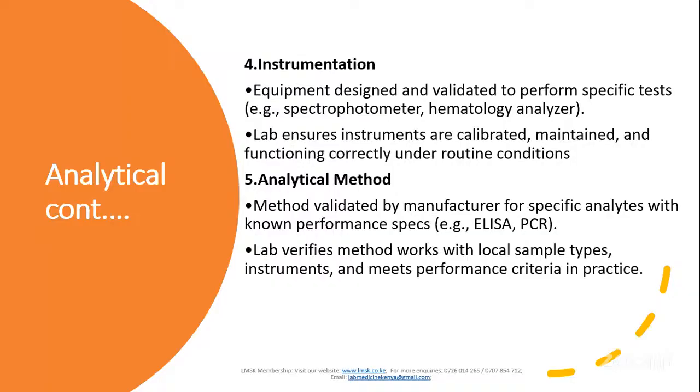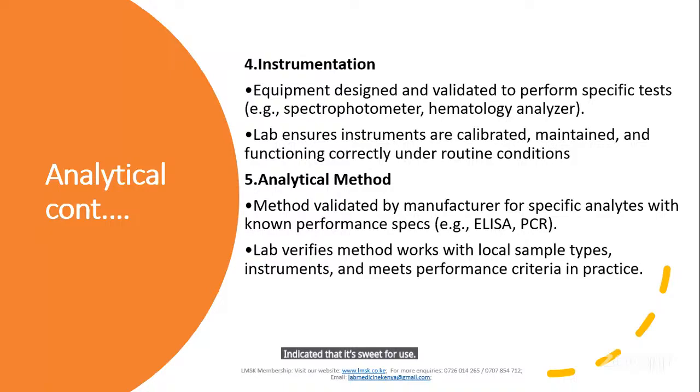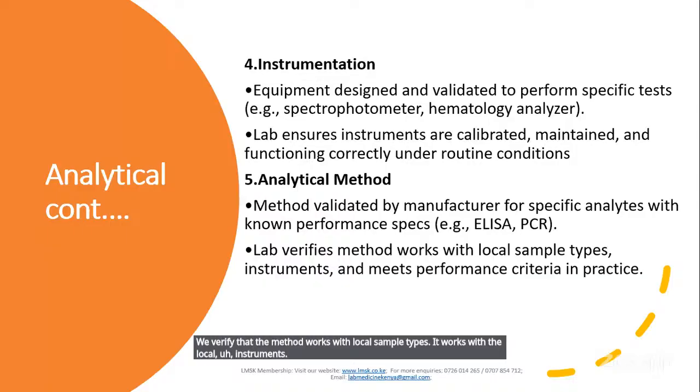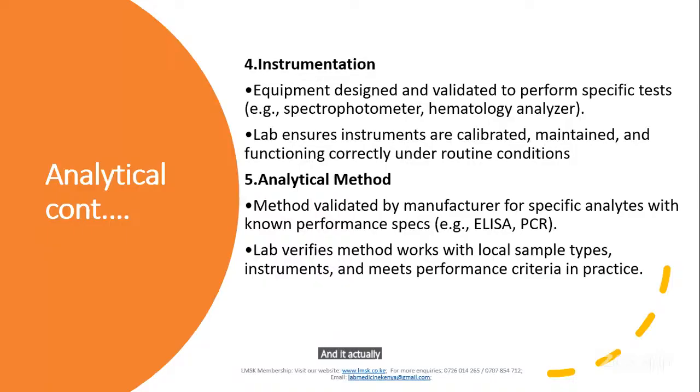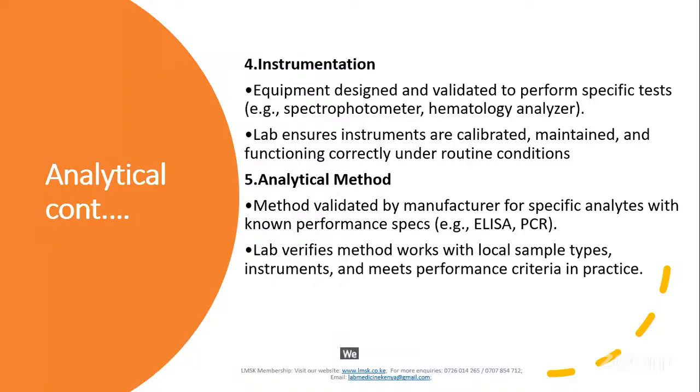The method validated by the manufacturer for specific analytes with performance specifications indicated there. It's fit for use. So we as lab personnel verify that the method works with the local sample types, works with the local instruments, and actually meets performance criteria in practice. Once we do that, what was declared as fit for purpose, we are translating it to fit for use.